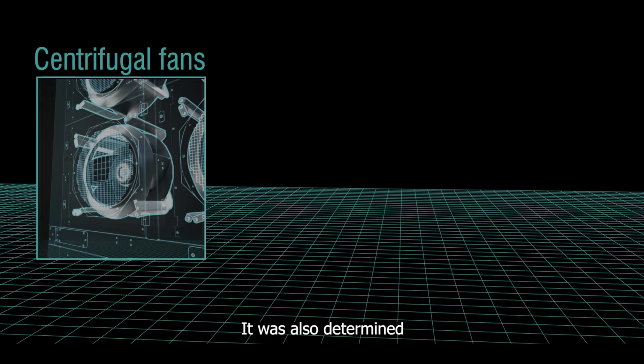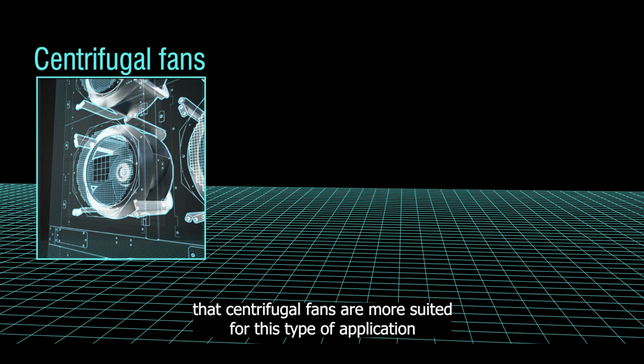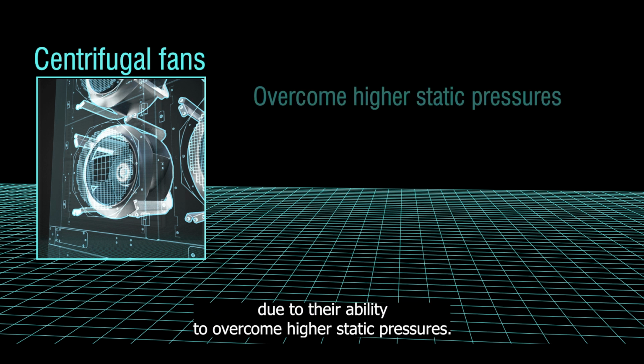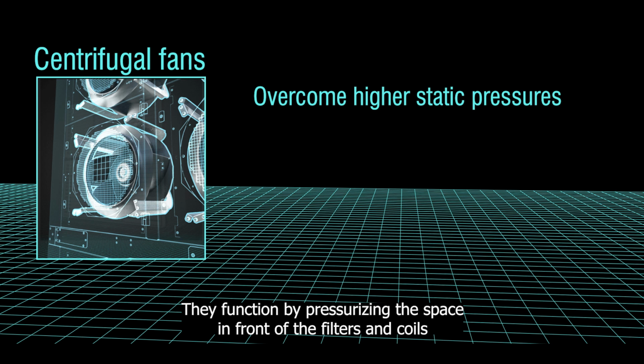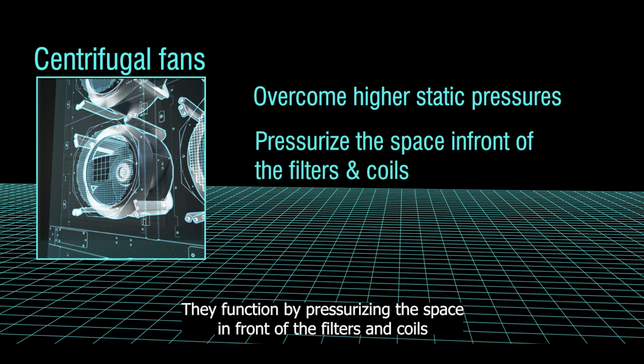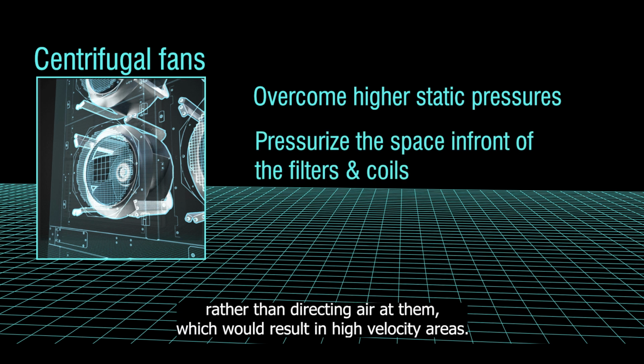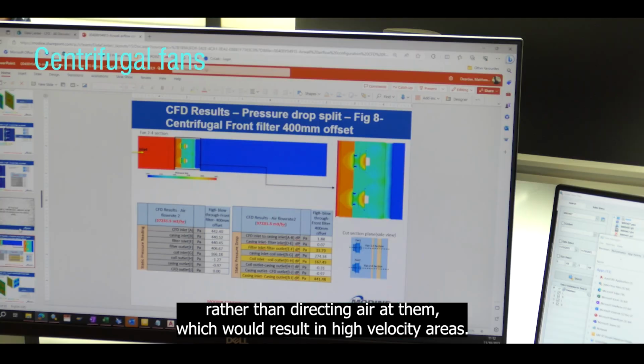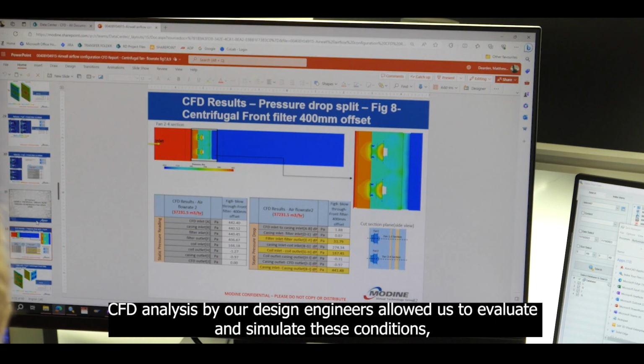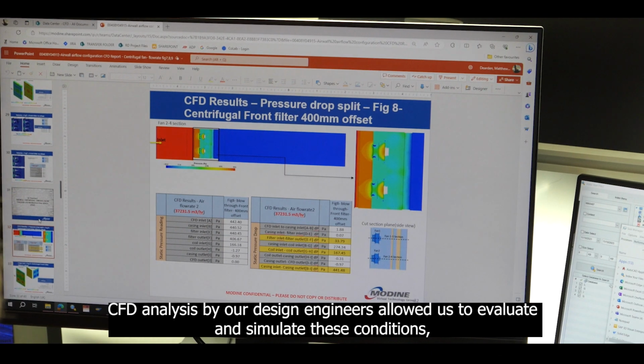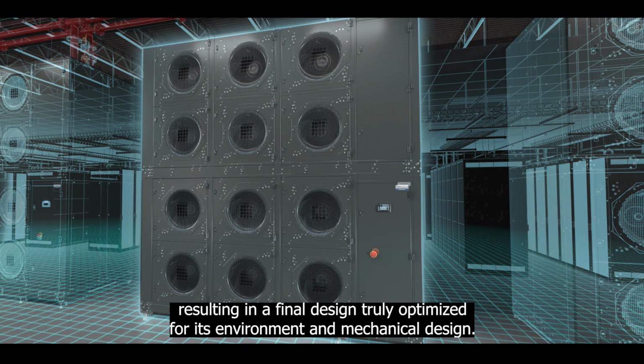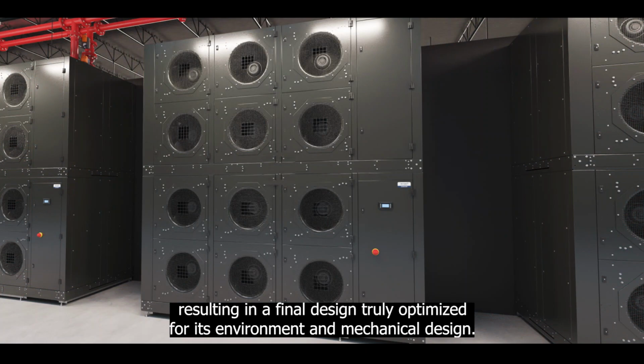It was also determined that centrifugal fans are more suited for this type of application due to their ability to overcome higher static pressures. They function by pressurising the space in front of the filters and coils rather than directing air at them, which results in high velocity areas. CFD analysis by our design engineers allowed us to evaluate and simulate these conditions, resulting in a final design truly optimised for its environment and mechanical design.